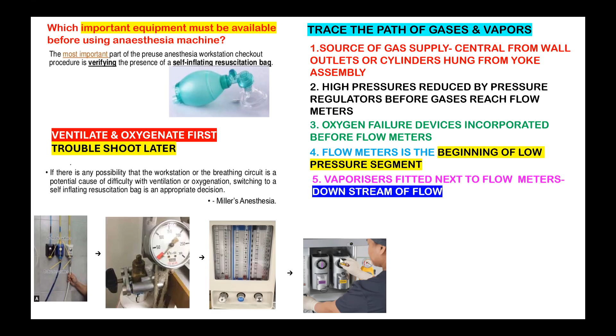Breathing circuit. Straight away breathing circuit? Don't you give sevoflurane or desflurane or isoflurane? Vaporizers. The vaporizer will be the next one. Okay. Yes, sir, I'm tracing the pathway. No, you are starting from the source, going through the pressure gauge, going through the flow meter, going through the vaporizer. If you don't want to use the vaporizer, well and good, you are not going to open it at all. But the next connection will be to the vaporizer. And then finally from the vaporizer only, we will go to the breathing circuit.